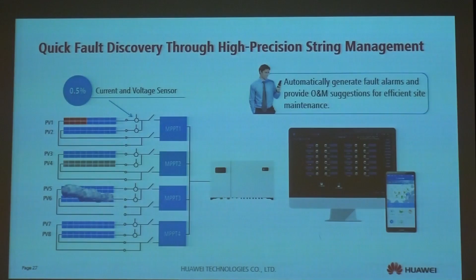This is a unique technology — we can realize the whole PV plant's IV curve diagnosis. Traditionally, if you want to do IV curve inspections, you need to send people on site with professional devices. After reaching the site, you need to plug out the strings and plug them into the devices. After several rounds, you collect the data, go back to the office to analyze it, and generate a report. Normally, they only take a 1 to 10% sampling test, and then give you a report.